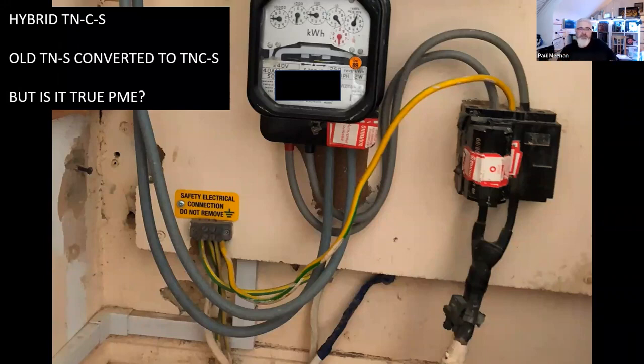But what is interesting is that during this research, in reading the DNO standards, the DNOs have created something which I term hybrid TNCS, where it's PILC at one point, and we've discussed this previously, and then the cables are repaired with a CNE or a PEN conductor style cable where it's TNCS, and you get a hybrid. Then you don't have that separation between your earth and neutral. It becomes a hybrid system. Is it really true PME though?